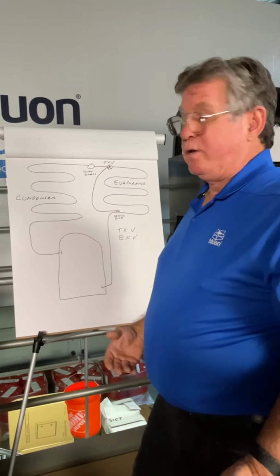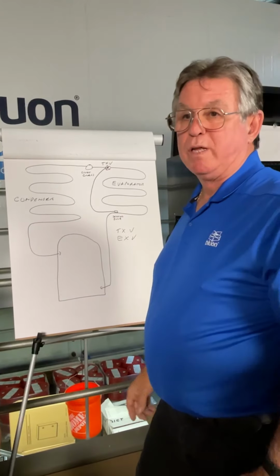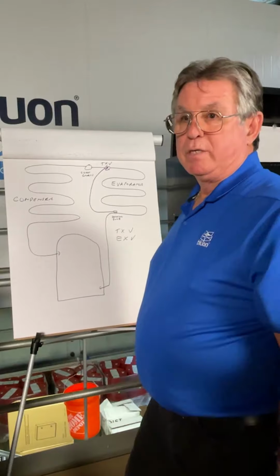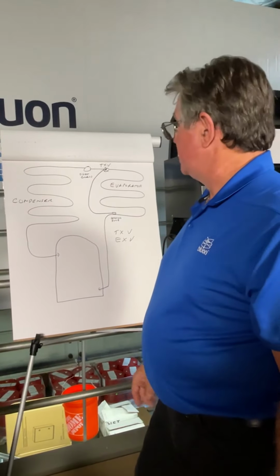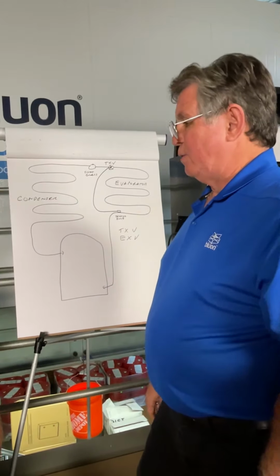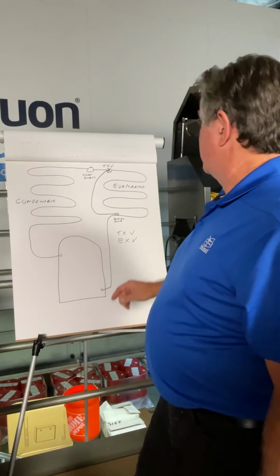An even better way to do it would be to measure your subcooling there and figure out where your subcooling is at. Typically, if you don't have a receiver, anything around 10 degrees of subcooling is great, all right?